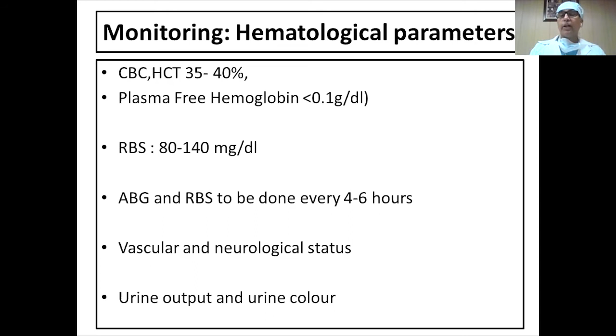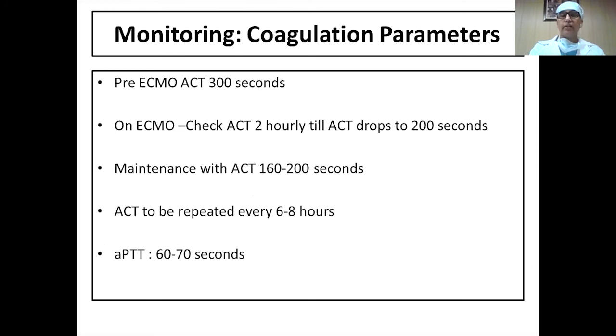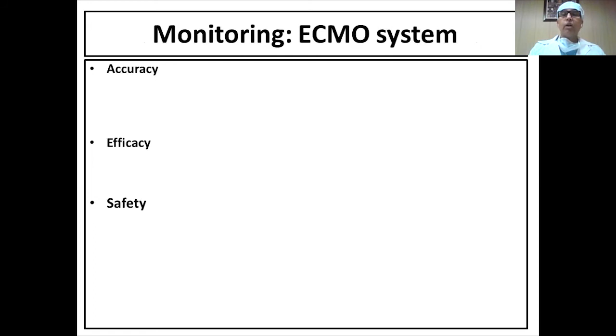We try to maintain the ACT around 160 to 180. We keep checking it, and APTT should be maintained at 60 to 70 seconds while a patient is on it. However, the advanced coagulation parameters should be monitored with the help of TEG or ROTEM or other devices. But these are the basics which should be followed at every place. Then we always look at monitoring the accuracy, efficacy, and safety of the ECMO system.